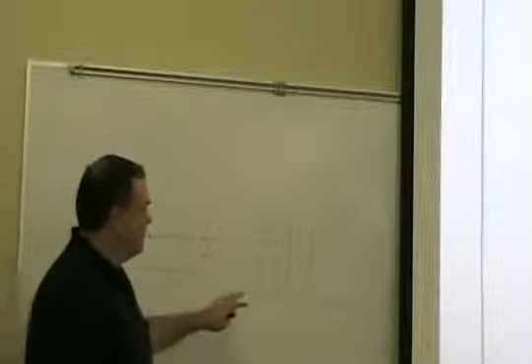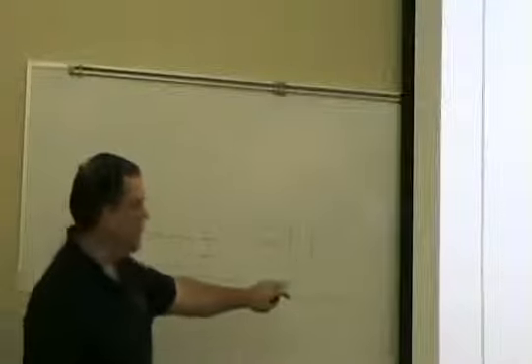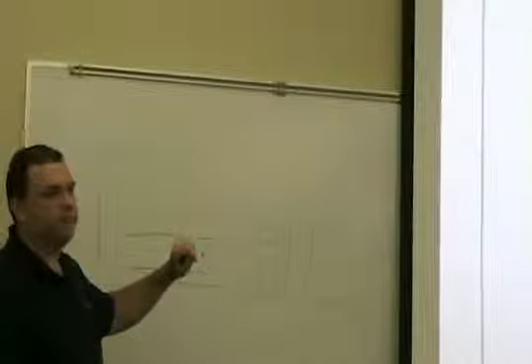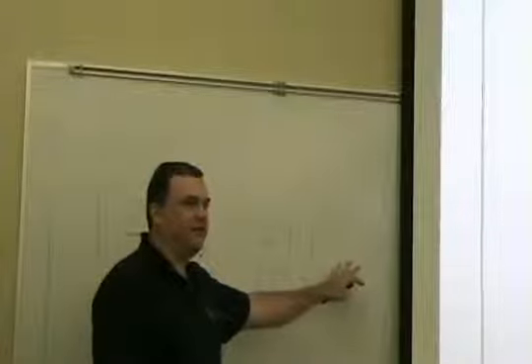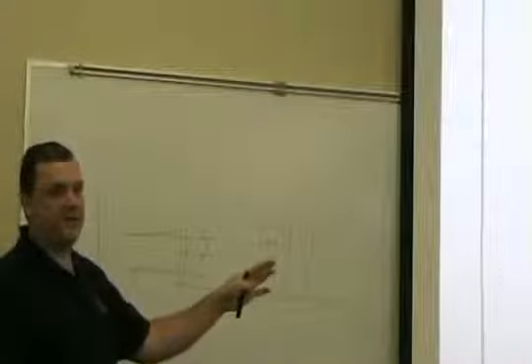Oh, yeah. But that could restrict airflow too. No, airflow's airflow. It wouldn't change the velocity at all? No. The only thing that's changing the velocity is the size of the duct. Okay? If you're putting 100 CFM here, it's got to come out over here. It may do it at a lower velocity or a higher velocity, but it's still going to be the same amount of airflow. Discounting any leaks or anything.